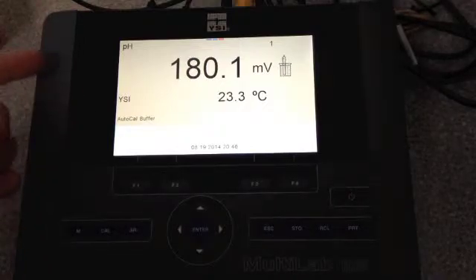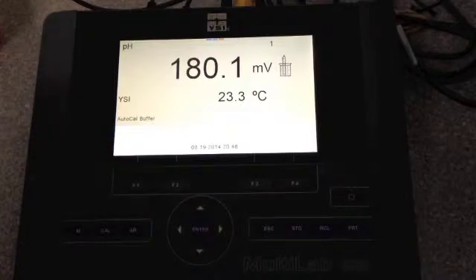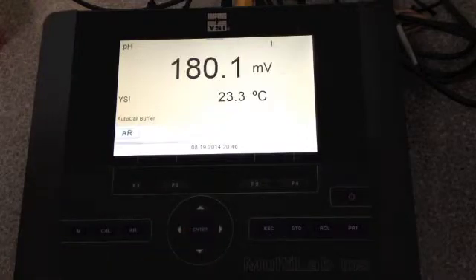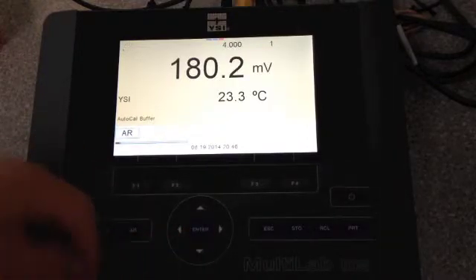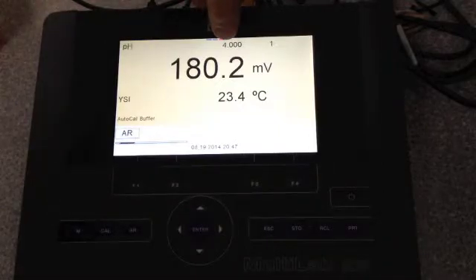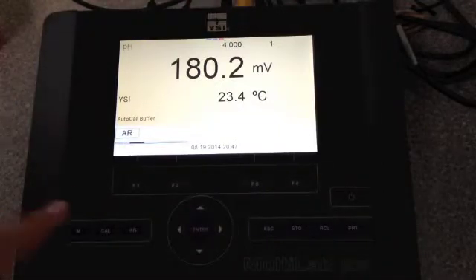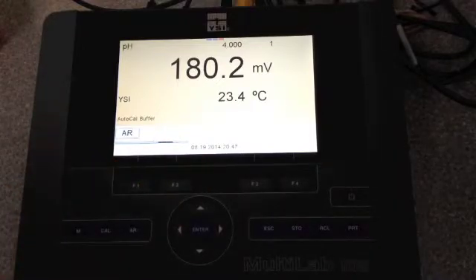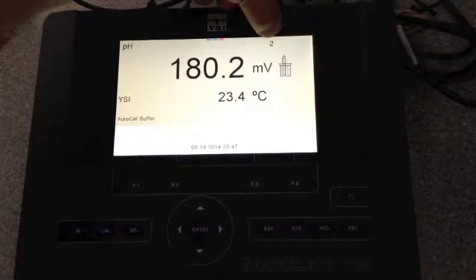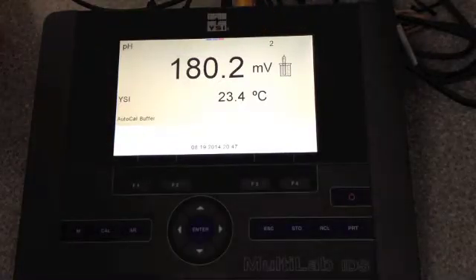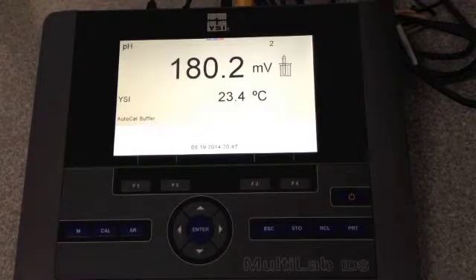So once we have our solution in the first pH buffer, we're going to hit the enter button. Right now it recognized the buffer as pH 4, and as you can see, it's doing the auto read on it. We're just going to do a 2-point calibration. After it beeps, it's asking for the second point. So I'm going to clean and prepare for our second and final point.